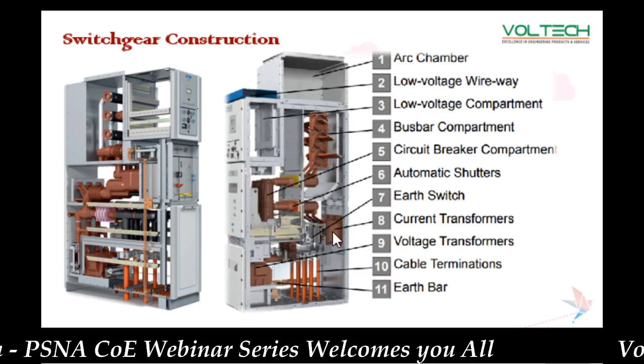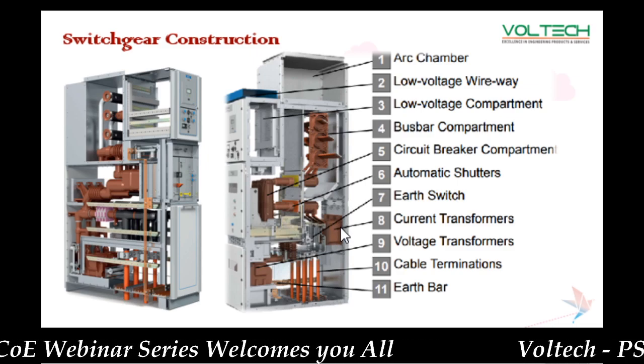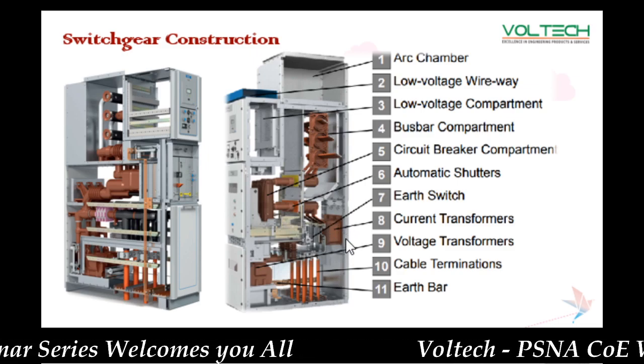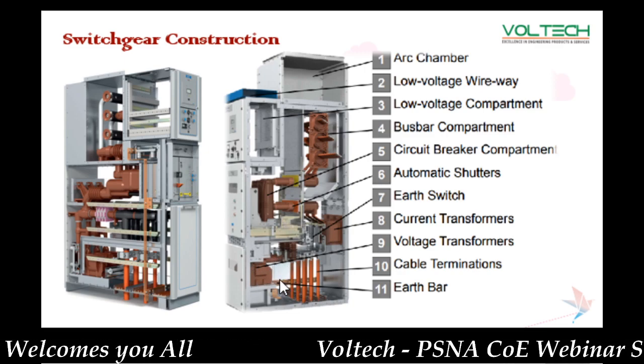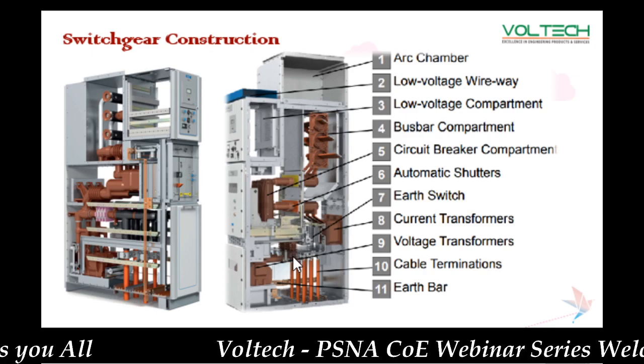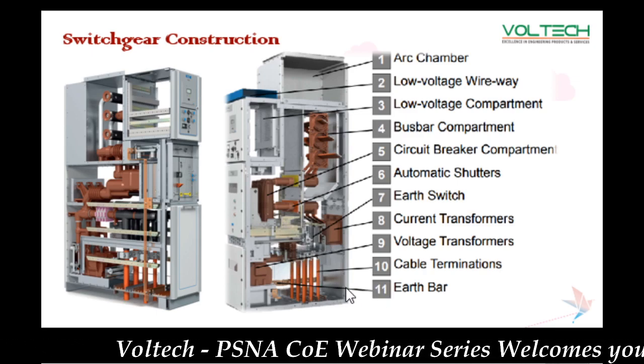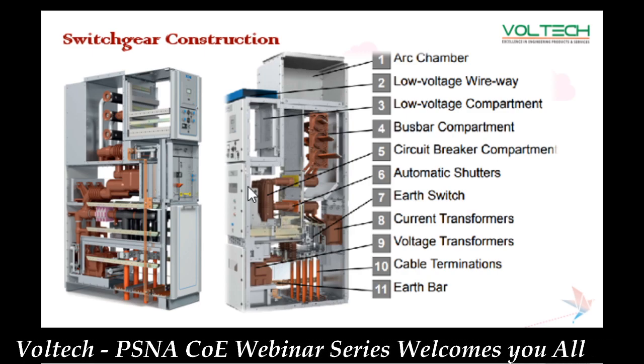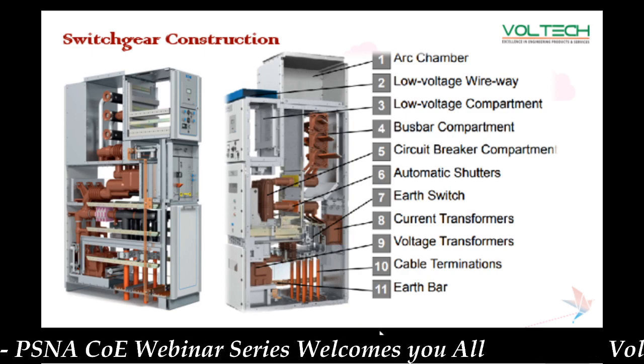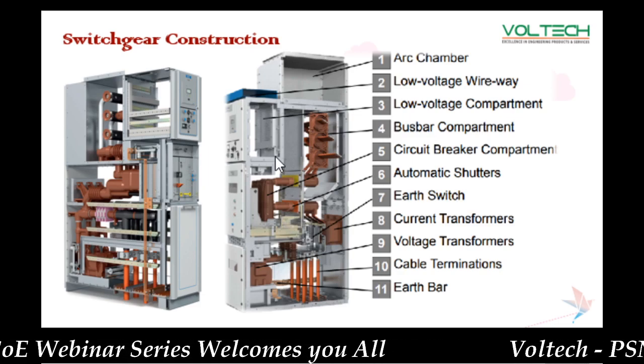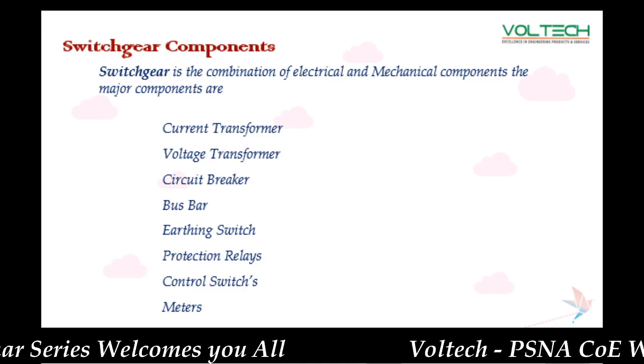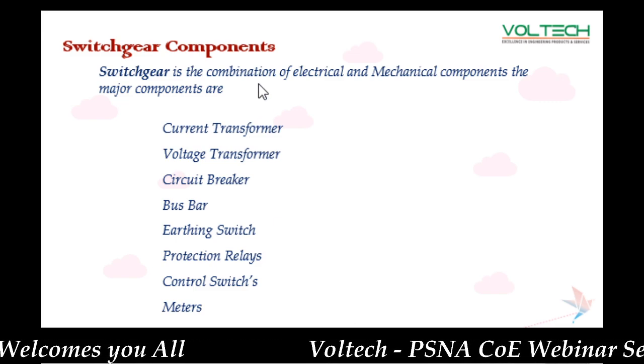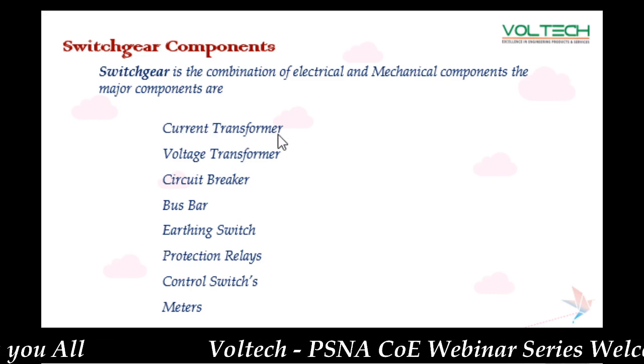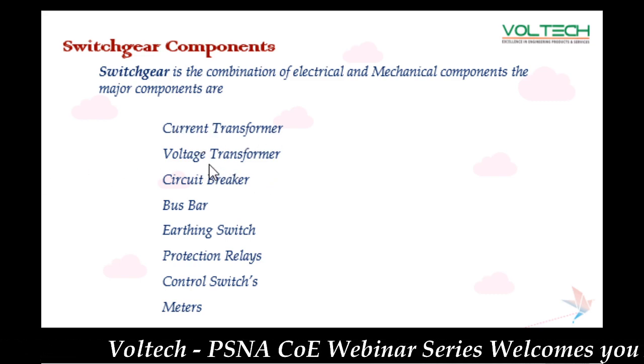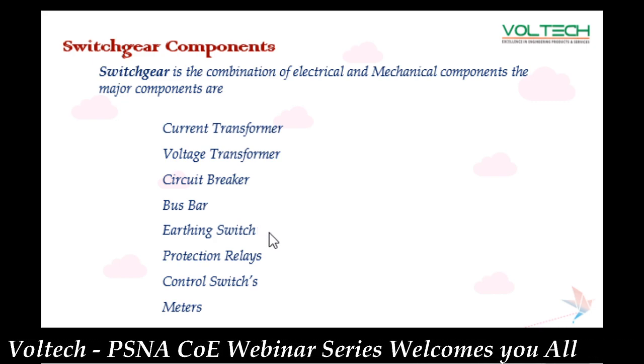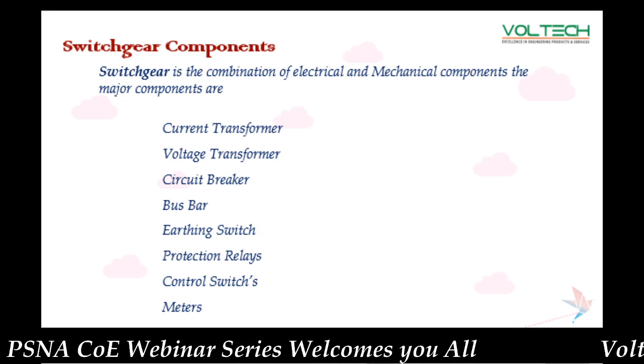This cable is connected here, and this is the current transformer which is used to measure the current, and this is the potential transformer, and this is the earth switch we are placing here. The earth switch is used for grounding the system, and this is the earth bar for this whole compartment. Next we talk about the other components in detail. We have some major components: current transformer, voltage transformer, circuit breaker, busbar, earth switch, protection relays, control switch, and meters. So now we talk about them in detail.